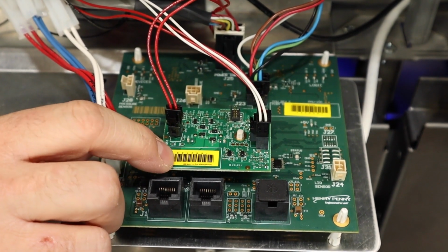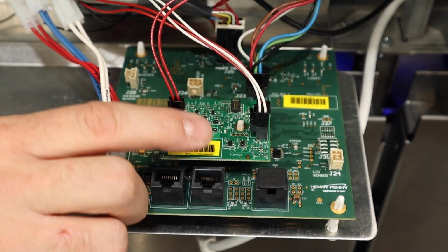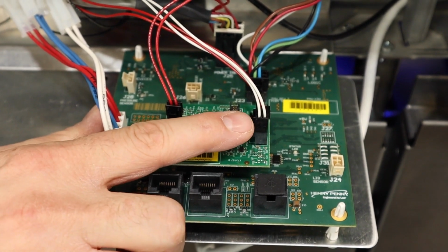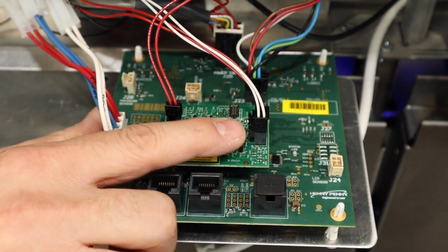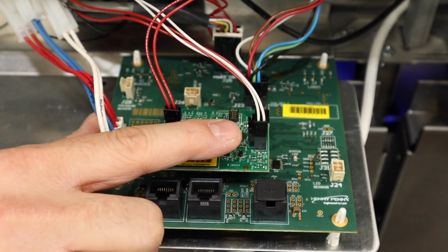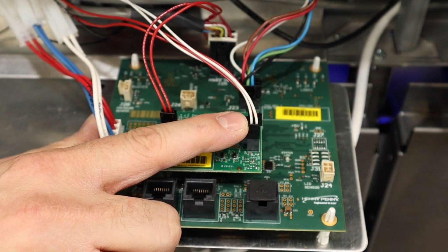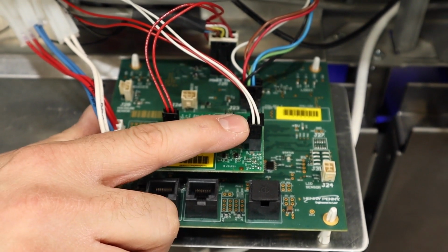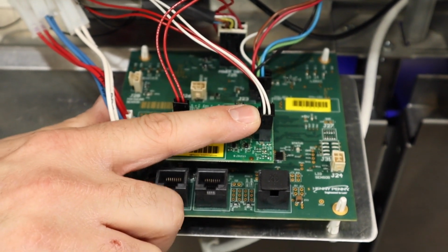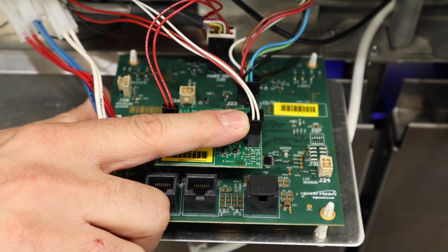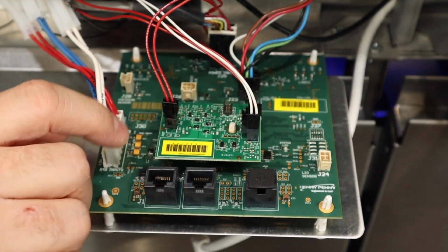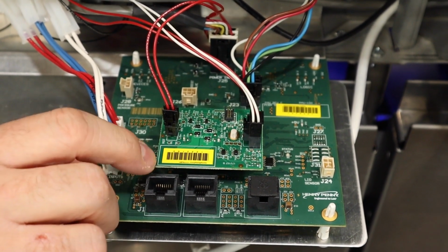So what we could do to troubleshoot that is, of course, power everything down for safety, unplug our probe connector right here. We could check our probes to make sure that they are working properly and they're calibrated. We could check that with resistance, make sure that they're not shorted. And if they're okay, then we know most likely it's our high limit PCB board.